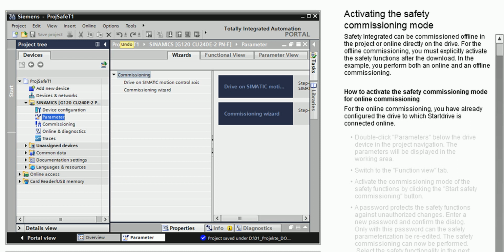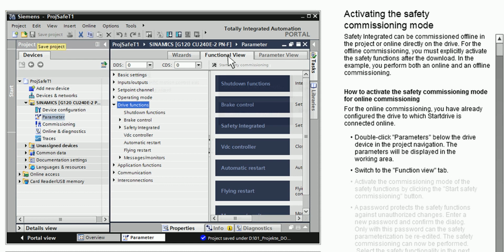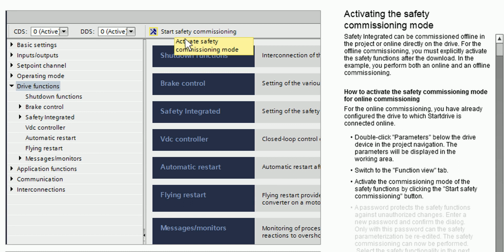How to activate the safety commissioning mode for online commissioning. For the online commissioning, you have already configured the drive to which Startdrive is connected online. Double-click Parameters below the drive device in the project navigation. The parameters will be displayed in the working area. Switch to the Function View tab. Activate the commissioning mode of the safety functions by clicking the Start Safety Commissioning button.